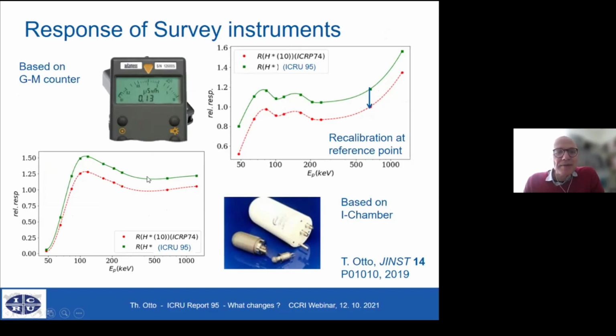The same is true for an instrument based on ionization chambers where the response is cutting off even earlier. These are ionization chambers which are filled with high pressure gases and therefore have 1 centimeter or even more wall thickness of stainless steel. So they really cut off low energy gamma rays and they can be simply recalibrated without loss of usefulness in their approved measurement range.